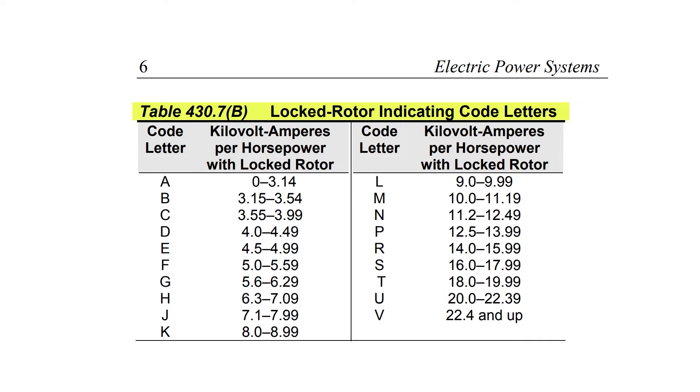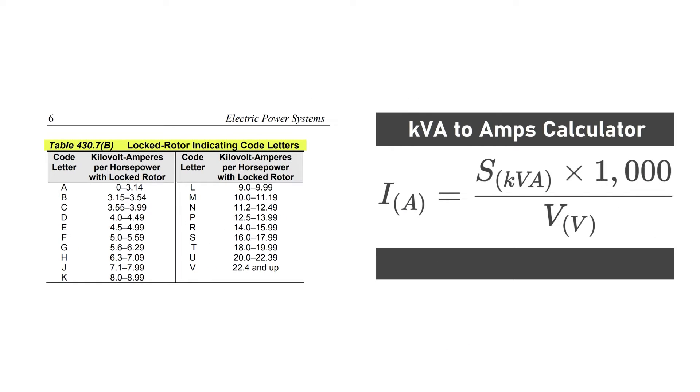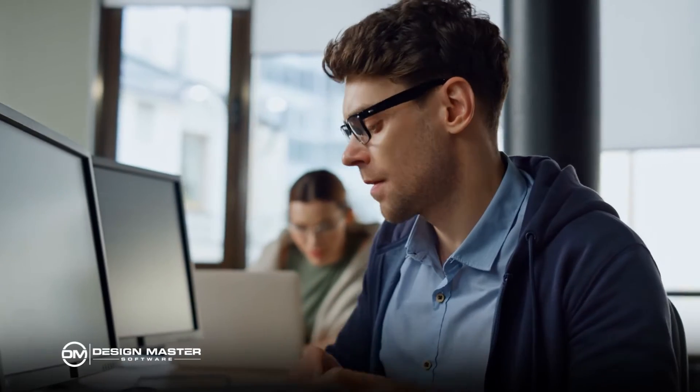Looking at that table, there's no current listed — only kVA per horsepower. The table is meant to be a little more universal. So if you know the horsepower of the motor, it gives you the kVA you can expect for the inrush current, and you have to convert it to current. When you convert it to current, you're going to get the numbers we've been talking about. The table avoids specifying voltage so it can remain universal.